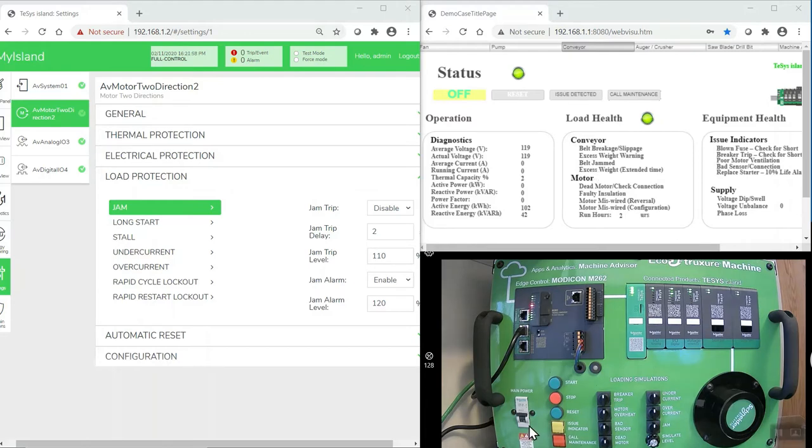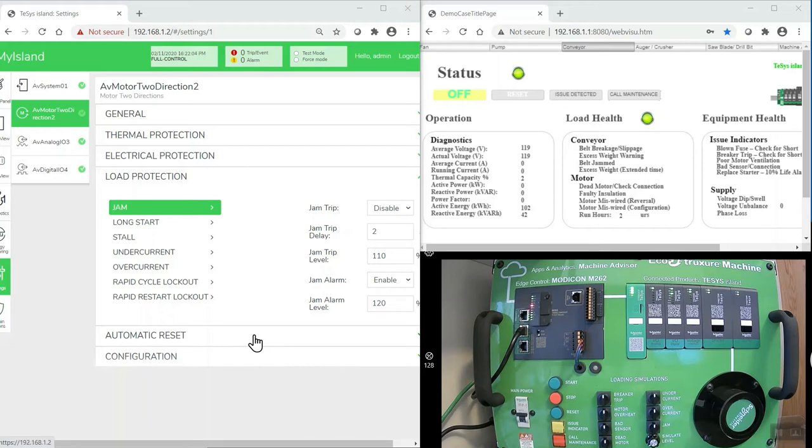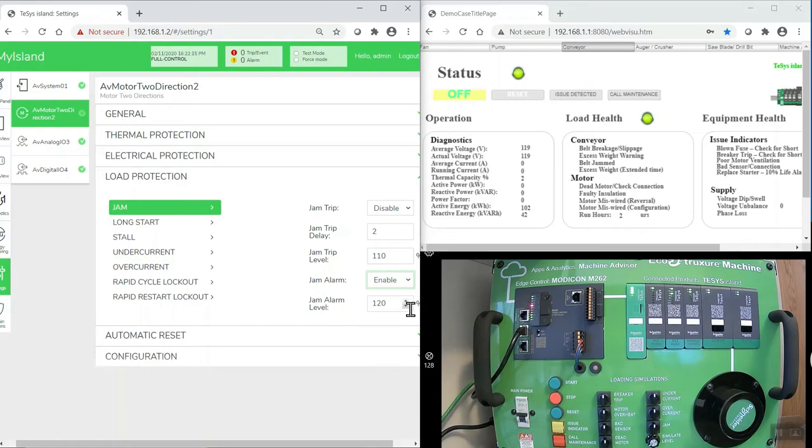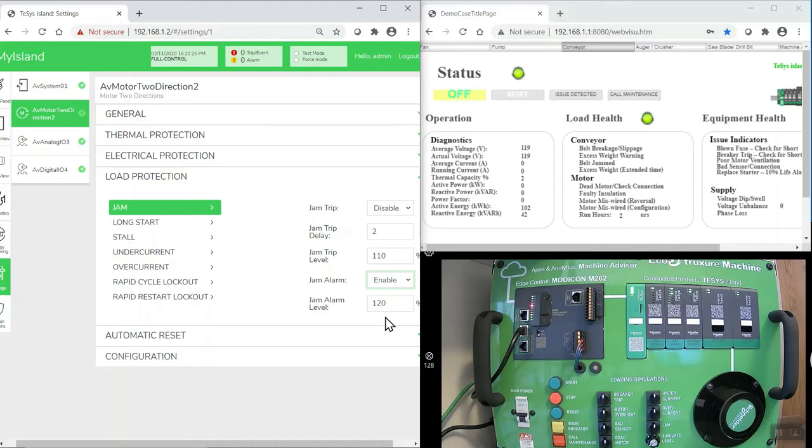With the TeSys Island demo unit powered up, we've logged into the device page using a laptop and an Ethernet cable and we've come over to the settings for the two-direction starter. I've set the jam alarm, enabled it, and I've set the jam alarm level to 120%, which is 120% of the full load amps of the motor. When the current reaches 120%, we're expecting an alarm to be triggered, but the motor not to stop.